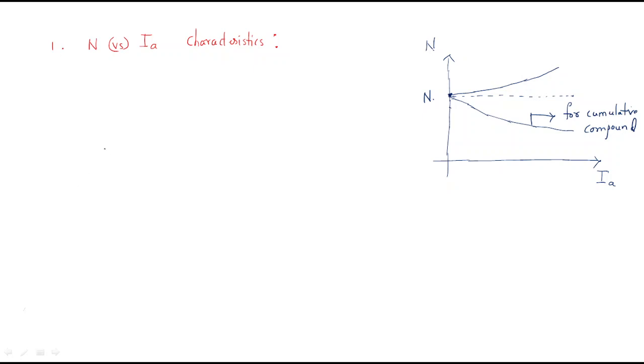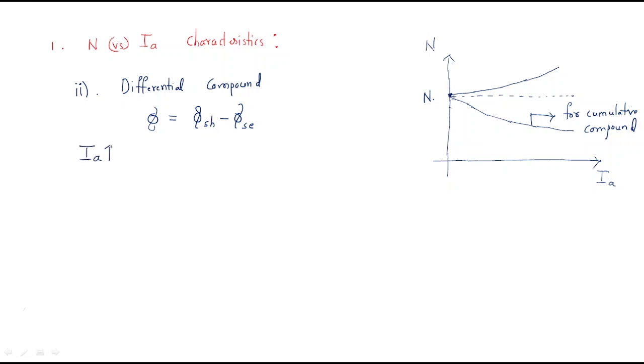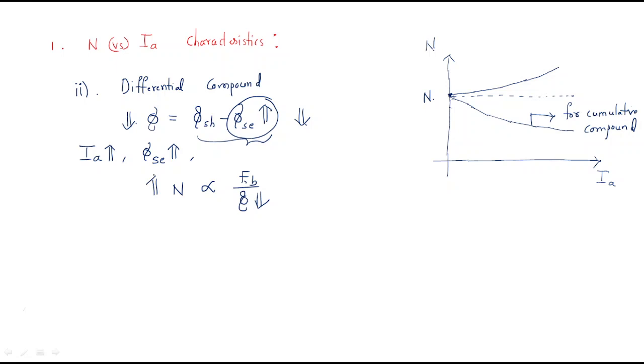Second case: differential compound motor. In a differential compound motor, the total flux is shunt minus series flux. Whenever the load current increases, the series flux also increases. When the series flux increases, the total flux (shunt minus series) decreases. Since N is proportional to Eb divided by total flux, when the total flux decreases, the speed increases.